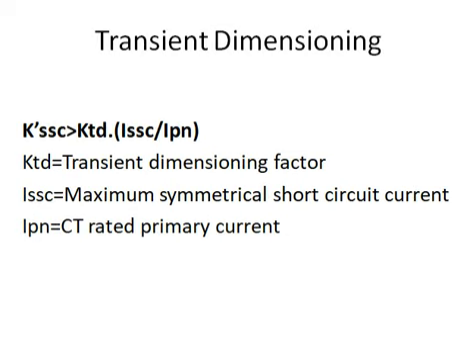After calculating K_SSC_dash, we need to check whether this effective symmetrical short-circuit factor is greater than or equal to KTD multiplied by I_SSC divided by I_PN. Here KTD is the transient dimensioning factor as defined in IEC 60044. This value is provided by the CT manufacturer and will be reflected in the technical particulars or CT catalogs. I_SSC is the maximum symmetrical short-circuit current and I_PN is the CT rated primary current. If this criteria is met, you can consider your CT selection is OK.